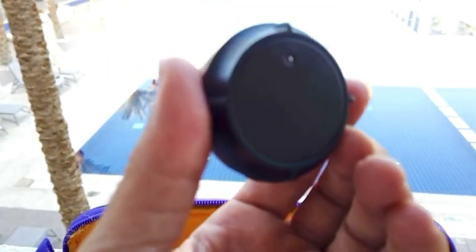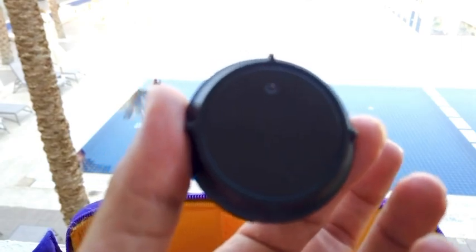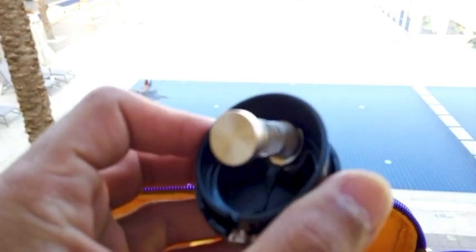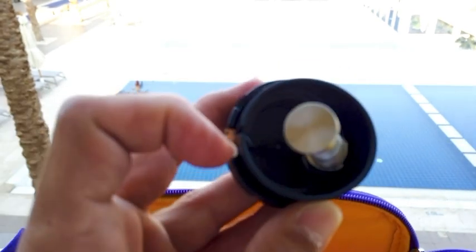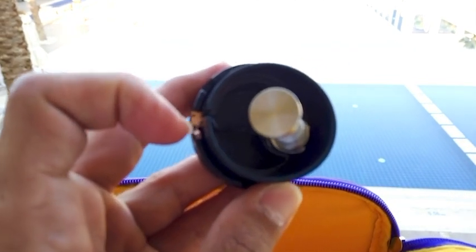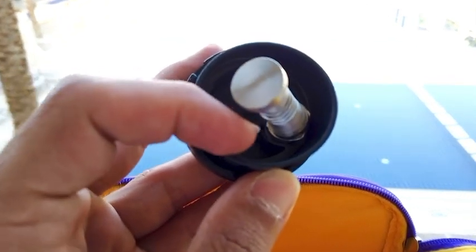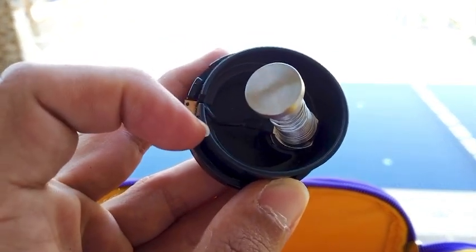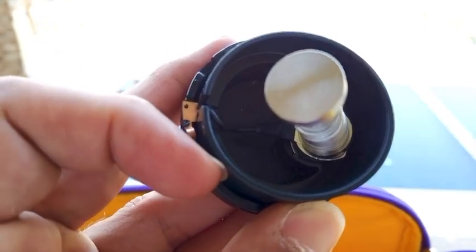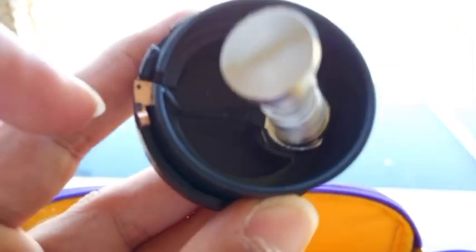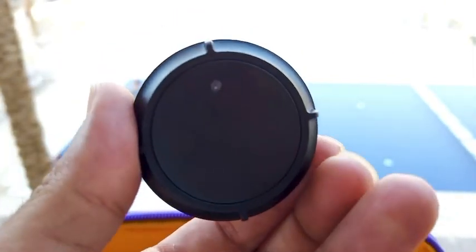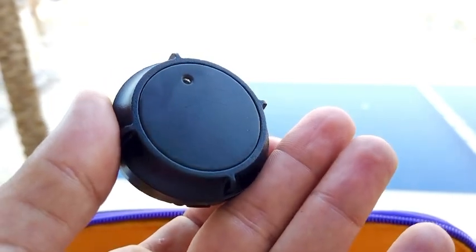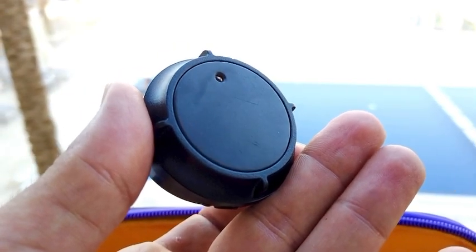Do you see there's one metal piece that doesn't have any pictures on the front? And when you look in the back, it has a middle cylinder. And when you look right here, do you see there's a wire that goes from here to here? So the one that has the wire, this is your calibration unit.